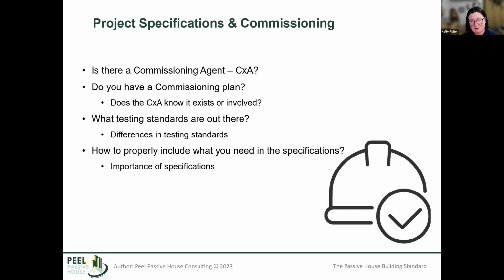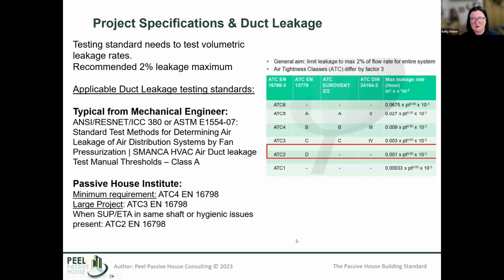Michael alluded a little bit as well to the different testing standards that are out there, and the importance of specifications, and knowing the difference between SMACNA, which uses area, and volumetric metrics to assess your leakage. We like to refer back to guidance from the Passive House Institute on this, where a recommended 2% leakage is the maximum. And this is all done to the EN standards that they provide as guidance for their assessment, which is EN 16798. You'll also get some typical duct leakage standard testing.